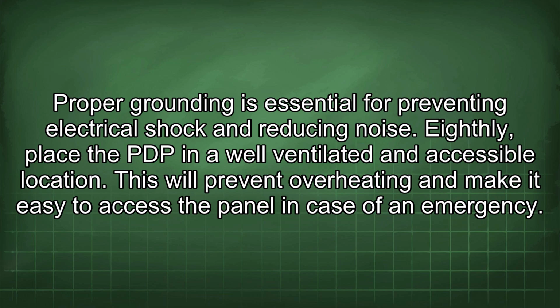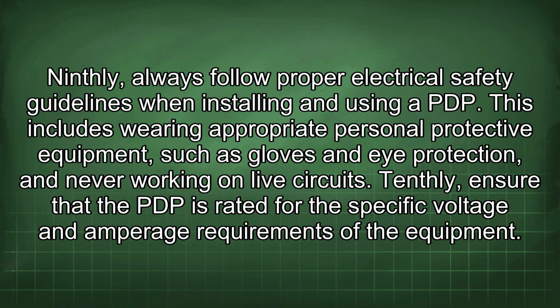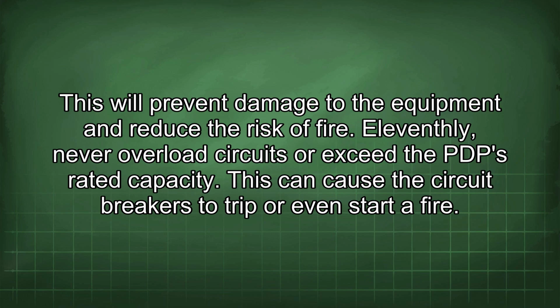Eighthly, place the PDP in a well-ventilated and accessible location. This will prevent overheating and make it easy to access the panel in case of an emergency. Ninthly, always follow proper electrical safety guidelines when installing and using a PDP. This includes wearing appropriate personal protective equipment, such as gloves and eye protection, and never working on live circuits. Tenthly, ensure that the PDP is rated for the specific voltage and amperage requirements of the equipment. This will prevent damage to the equipment and reduce the risk of fire.